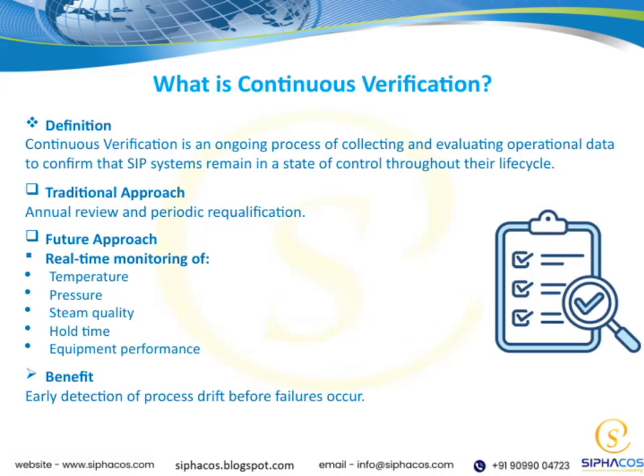Let's talk about continuous verification. It's an ongoing process where we collect and analyze operational data to make sure SIP systems stay in control throughout their entire life cycle. Traditionally, this meant annual reviews and occasional requalification. But the future is all about real-time monitoring, tracking temperature, pressure, steam quality, hold time, and equipment performance continuously. The big benefit: we catch any process drift early, before it turns into a failure.